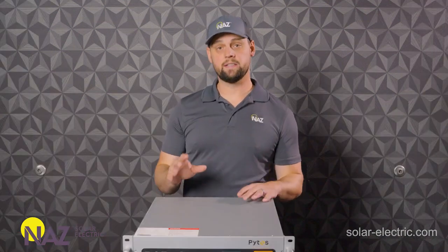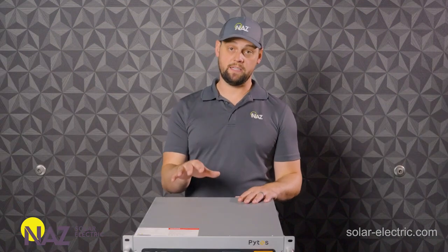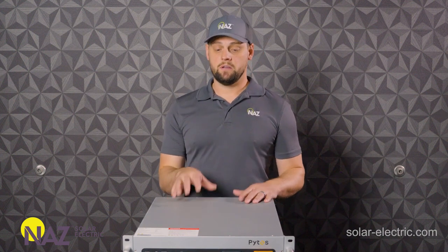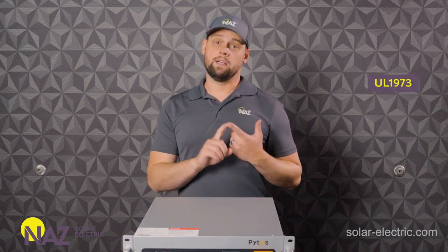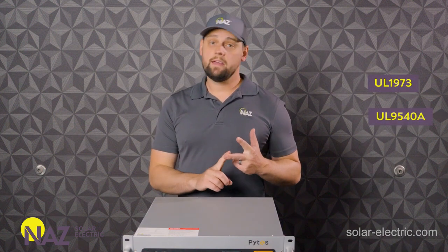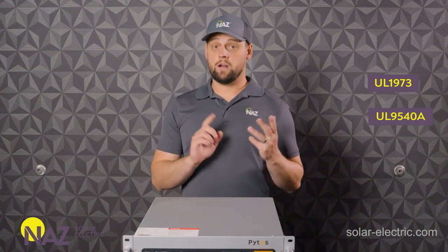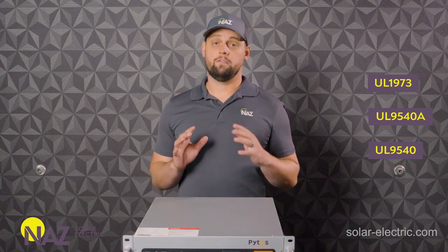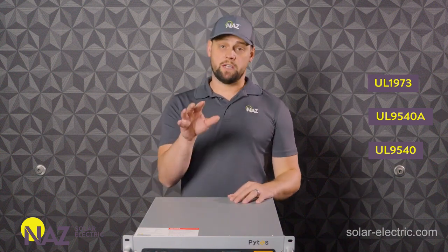These batteries have gone through rigorous third-party safety testing by nationally recognized testing laboratories. They are UL 1973 listed, they have gone through UL 9540A testing for thermal runaway, and they are UL 9540 listed with a variety of very common inverters — for example, Solark.